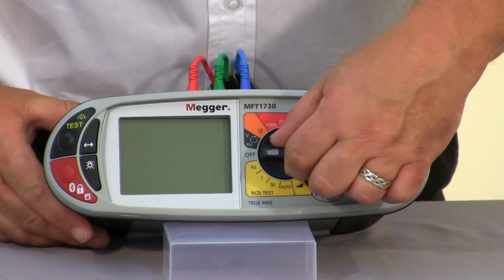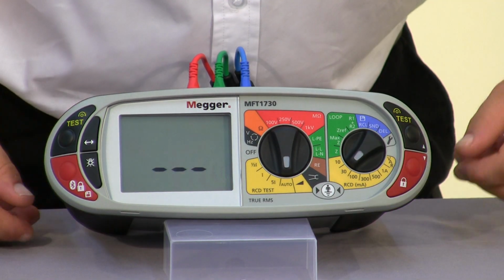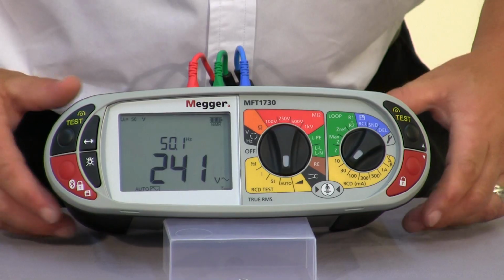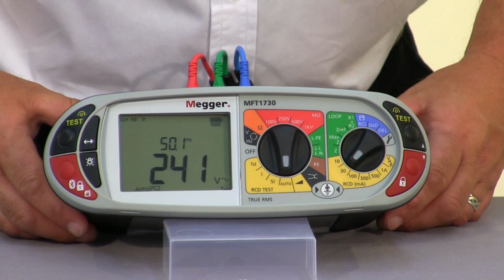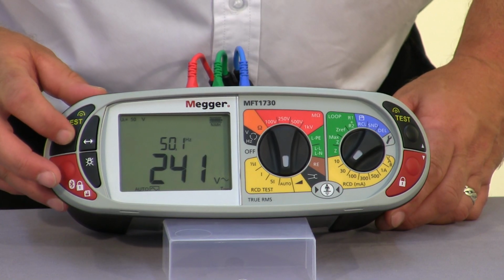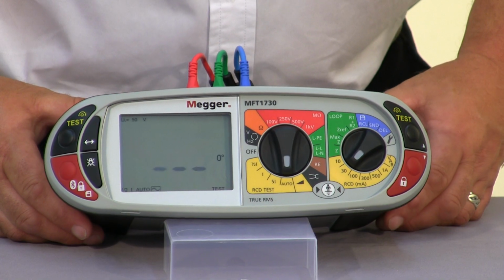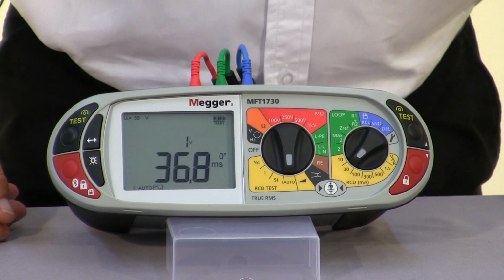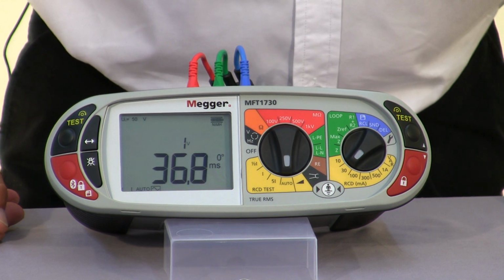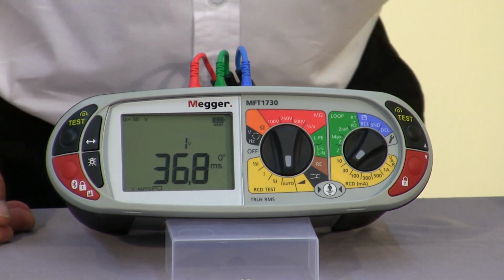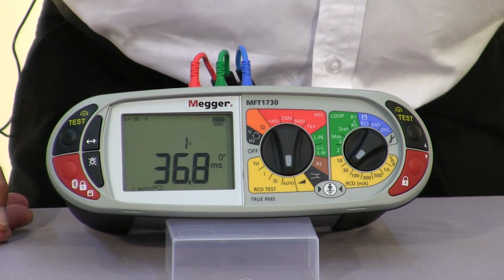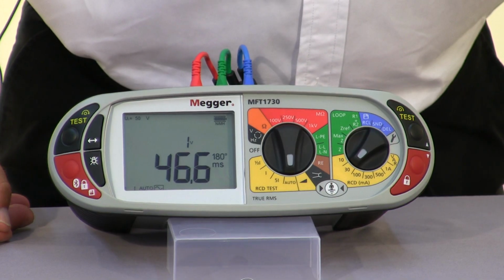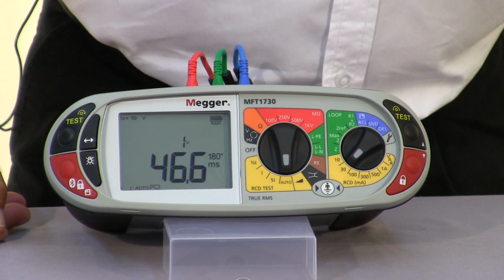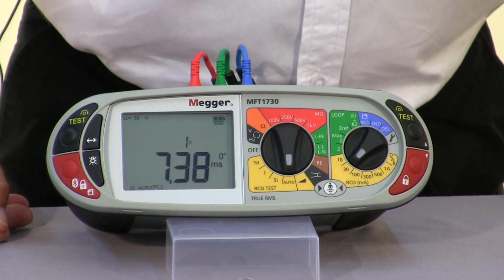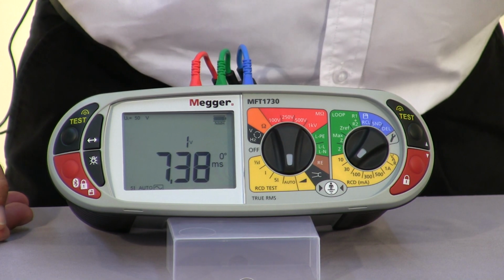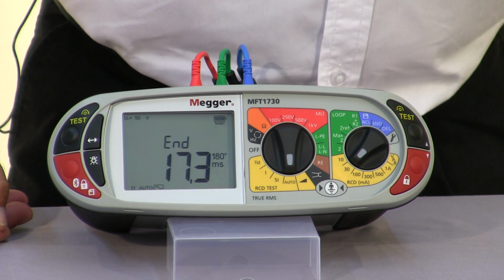So what I'm going to do is I'm going to select the auto test for a 30 milliamp RCD. Now you can set the MFT to auto start, but I've got this defaulting to a manual start. So initiate the test sequence, and it will then run through all the required tests. So in the first instance, we're making sure that the unit doesn't operate with a times half test. It's then gone straight in and done a times one test at zero. So resetting the RCD, it will repeat the times one test at 180 degrees. Reset again, and it ups to five times the rated current at zero, and finally five times at 180.